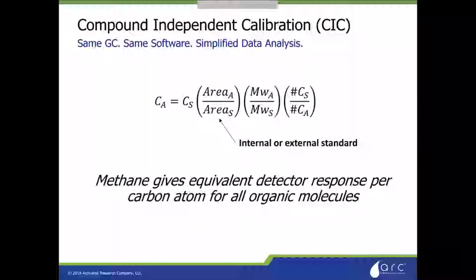And the most important part of the PolyArc is the uniform response that you're getting because of methane. And that means that quantification is as simple as looking at the relative areas relative to an internal or an external standard. So you do a single calibration with an internal or external standard, and you have an incredibly accurate quantification of all of those species.